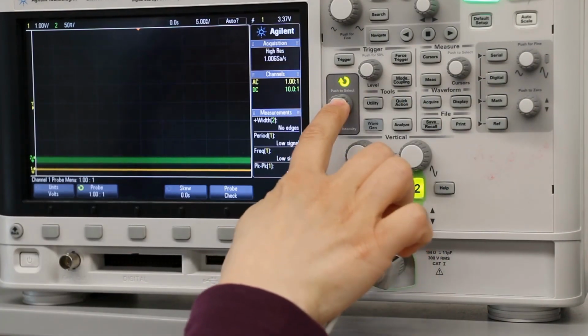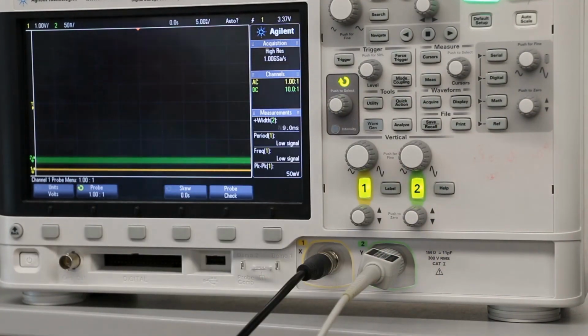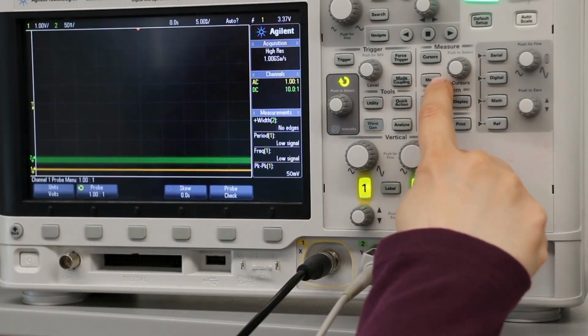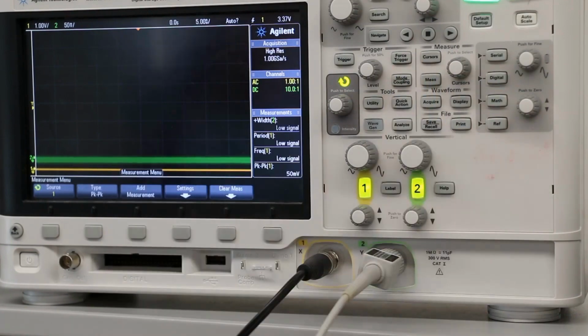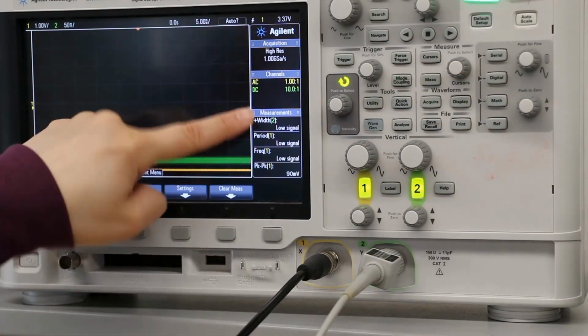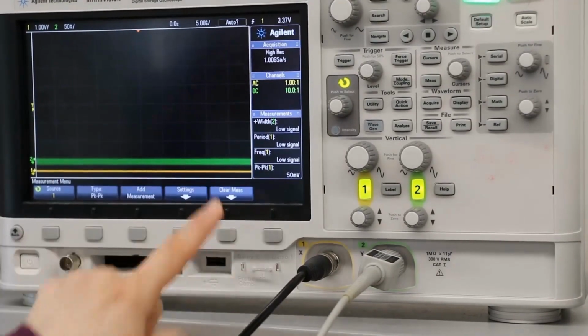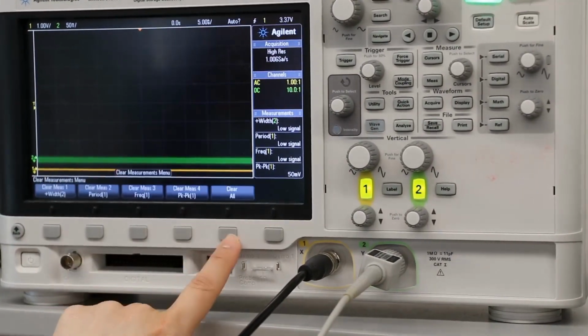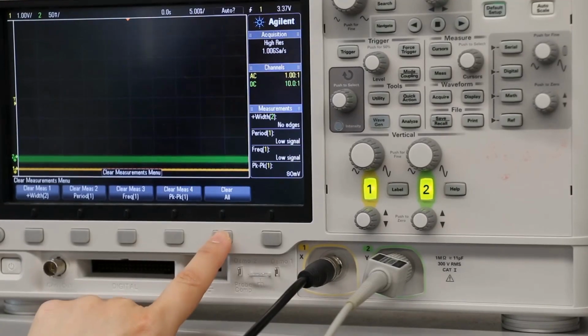Second thing, we need to measure the peak to peak and the frequency for both channel 1 and channel 2. So how to add the measurement? Here we find the measurement key. Press measurement, and we notice that we have old measurements. So first we need to clear all the old measurements. So clear measurements, and then clear all.